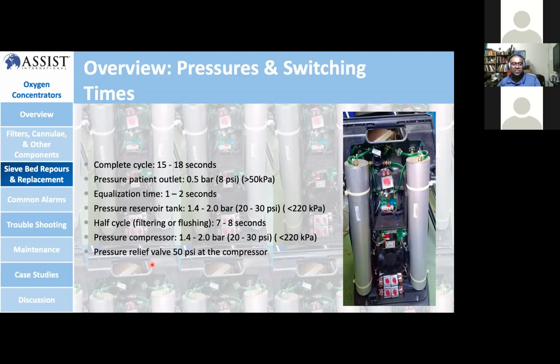Filtering and flushing. The bottom valve should work somewhere 7 to 8 seconds. And the compressor pressure should be somewhere 20 to 30 PSI for the complete unit. And the pressure relief valve on the compressor should be 50 PSI. So when you do all these tests, you need to comply with these readings. If this works properly, that means it's good.